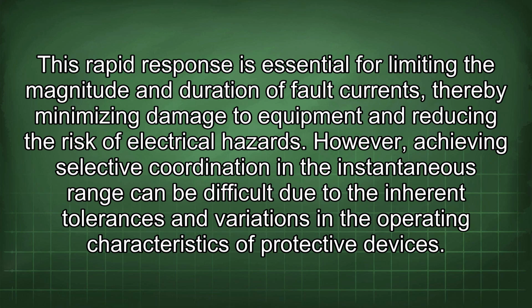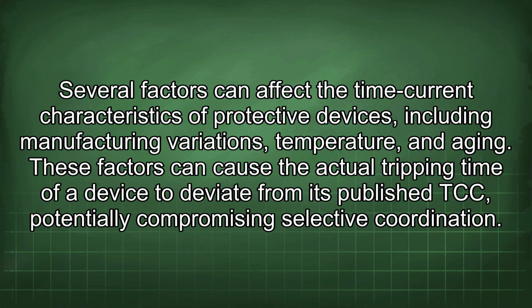However, achieving selective coordination in the instantaneous range can be difficult due to the inherent tolerances and variations in the operating characteristics of protective devices. Several factors can affect the time current characteristics of protective devices, including manufacturing variations, temperature, and aging. These factors can cause the actual tripping time of a device to deviate from its published TCC, potentially compromising selective coordination.